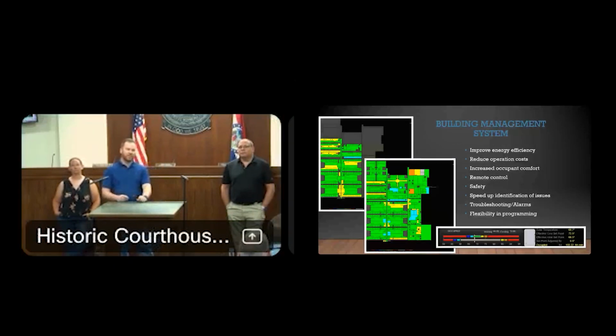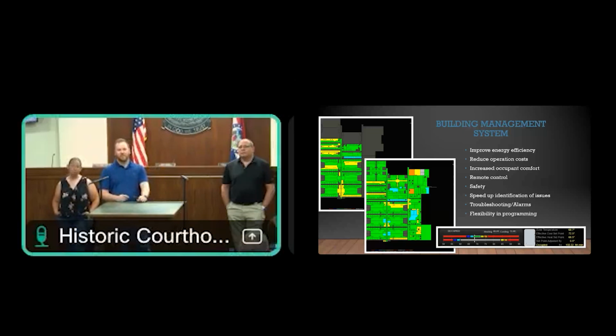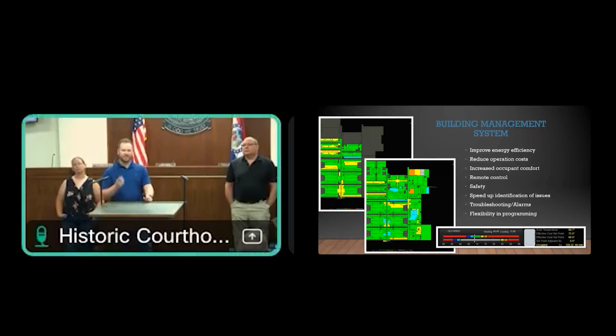One of the big components that we utilize daily is our building management system. Primarily it's for our HVAC team, but this helps with improving efficiency, reducing operation cost, and gives increased occupant comfort. We can change set points and change thermostats remotely. It's also for safety, so part of the fire smoke system at the jail goes through the building management system. The chart you see on the left is a representation of the jail. At the bottom right, if it's green, it's usually right at the temperature set point. The farther away from the green, the colder or warmer it is, and that's a quick indicator. If we see some red, we need to go look at that area.